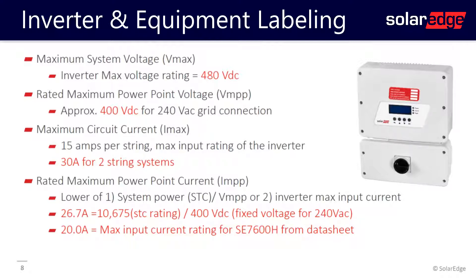The VMAX for a SolarEdge inverter can be found on the spec sheet. For this inverter here, the 7.6 kW HD Wave, the VMAX is listed as 480 volts DC. The VMP is also listed on the spec sheet as 400 volts DC.